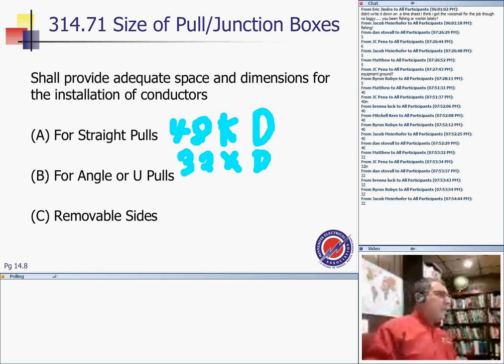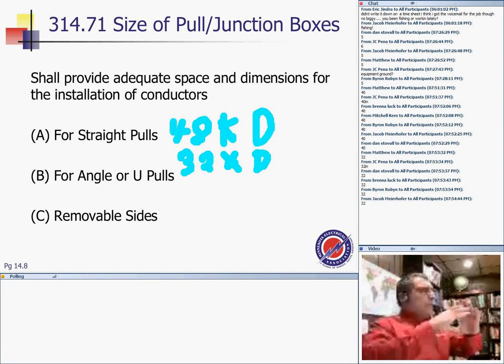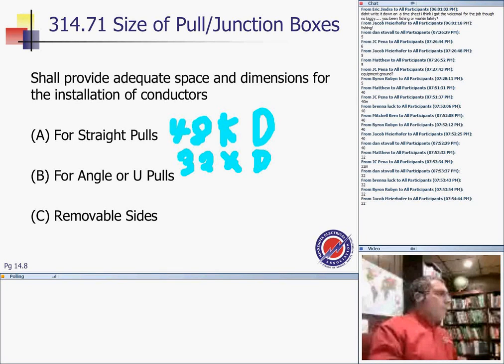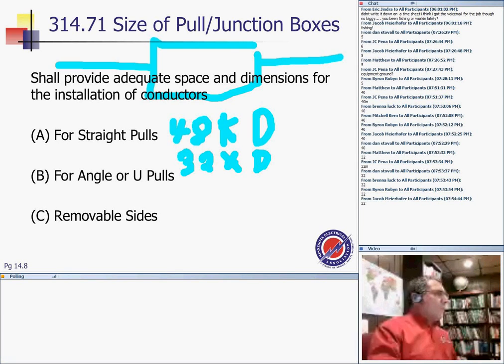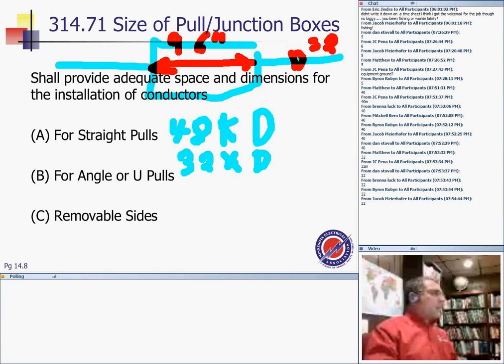Most of them are going to be shielded cables, guys, except a few applications for non-shielded. So here you go, Matthew, you have the cross-section area, your diameter of your cable is, say, 2 inch, multiplied by 48, and that will get you a straight pull. Here's a box. I pull medium voltage cable from here, and I need to find that distance. If the diameter of this was just, say, 2 inches, that will get me 96 inches. So that would be 96 inches wide.